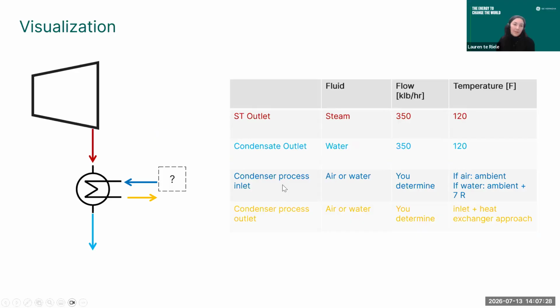If you had an infinitely large cooling tower, your water outlet temperature could be the same as the air temperature, but that's not necessarily economical. So 7 degrees is a pretty typical value for that temperature difference. That's a trade-off students can consider: the benefit of water being more effective for heat exchange, but you have to start with a higher temperature than for air.